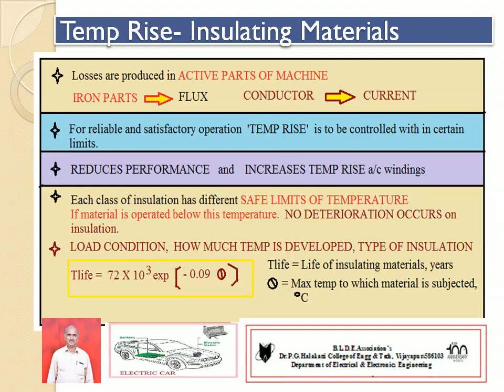Last point, at load condition, how much temperature is developed depends upon the type of insulation. The type of insulation should be selected considering electrical stress, mechanical stress, and the loading condition. Hence, the life of insulation is given by the following expression: T life equals 72 into 10 to the power of 3 times exponential of minus 0.09 times theta. T life is the life of the insulating material in years. Theta is the maximum temperature rise to which the material is subjected.